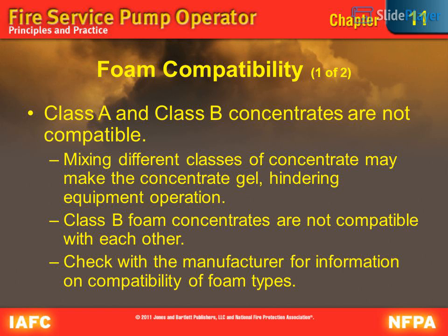Foam compatibility, 1 of 2. Class A and Class B concentrates are not compatible. Mixing different classes of concentrate may make the concentrate gel, hindering equipment operation. Class B foam concentrates are not compatible with each other. Check with the manufacturer for information on compatibility of foam types.